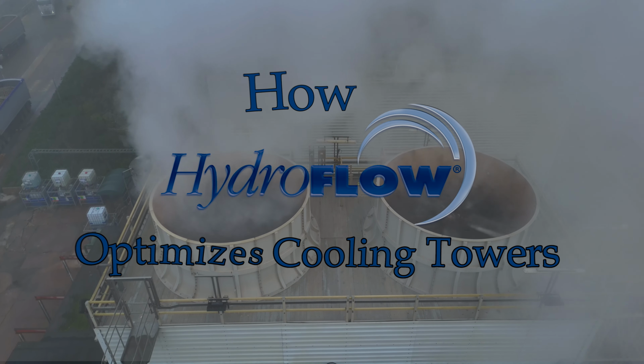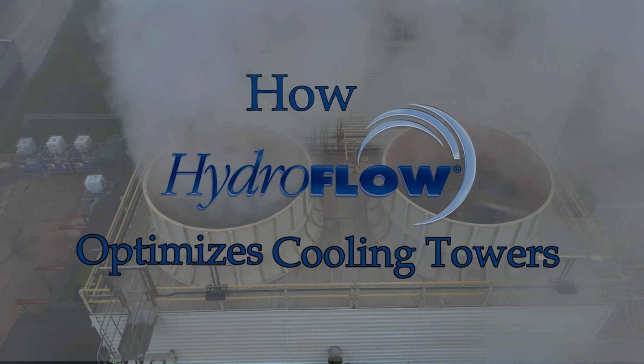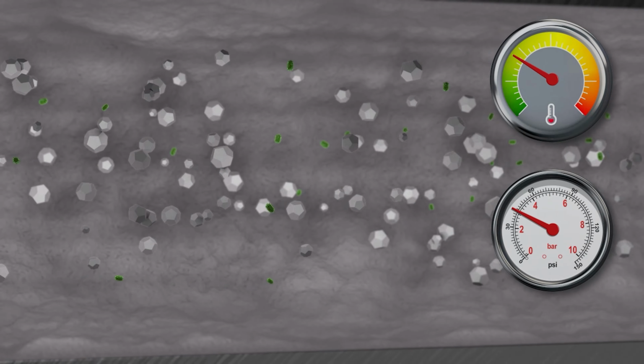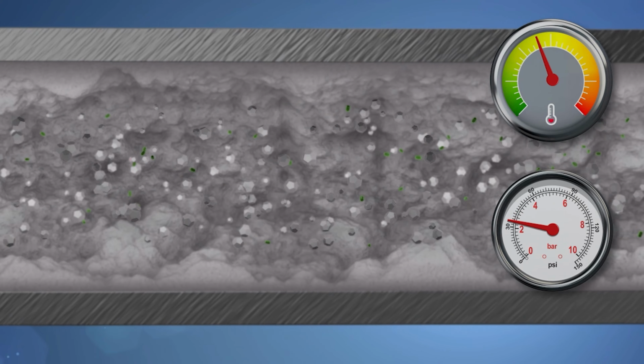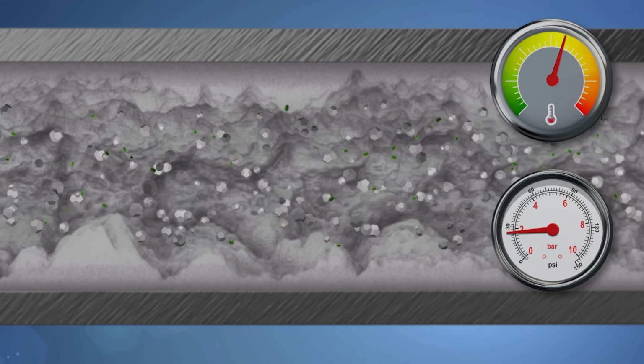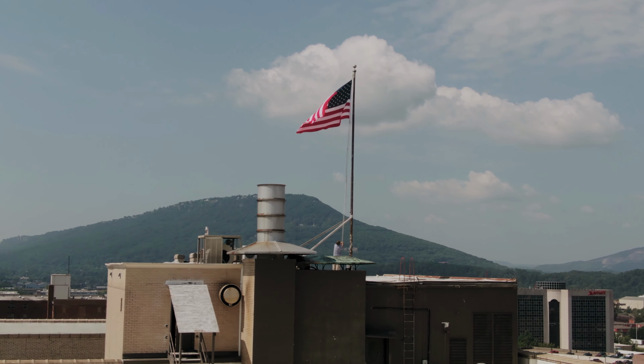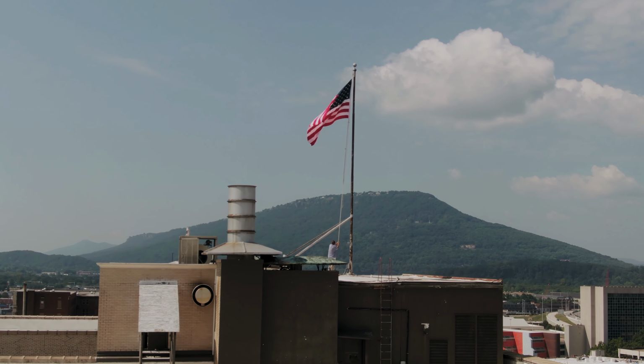How HydroFLOW optimizes cooling towers. Cooling towers expel heat through an evaporation process that increases the water hardness and causes scale to form. In addition, cooling towers utilize air from their surroundings to cool the water. This process introduces pathogens into the recirculating water system, which is a perfect breeding ground for bacteria and algae to thrive and accumulate as biofilm.